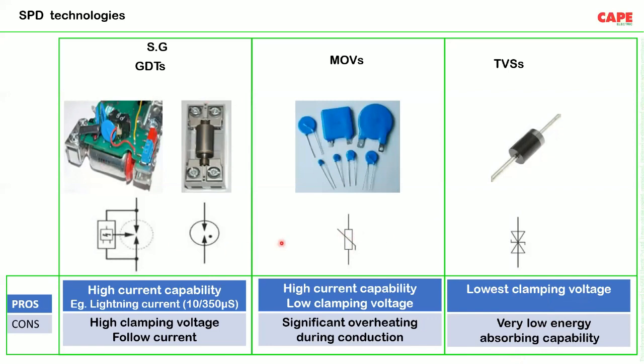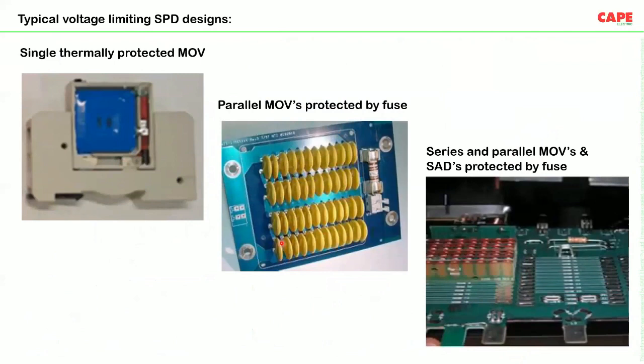These three are the components which are used in an SPD. You are seeing one of the constructions of an SPD, for example a single thermally protected MOV, and here there is the spring arrangement which I have told. This is one of the methods. The second method is parallel MOVs. A lot of MOVs in parallel series combination, and silicon avalanche diodes in parallel series combination.